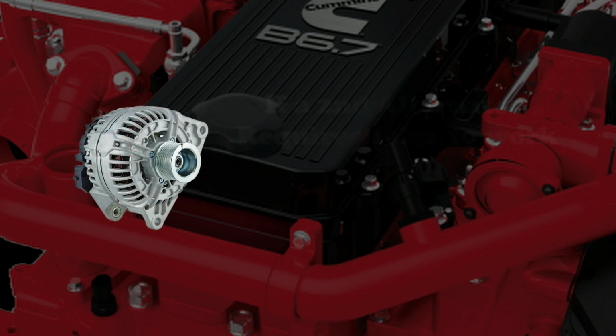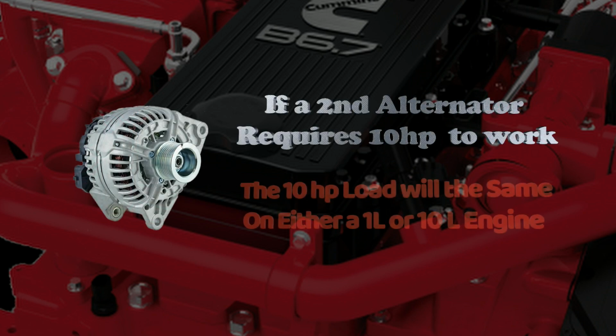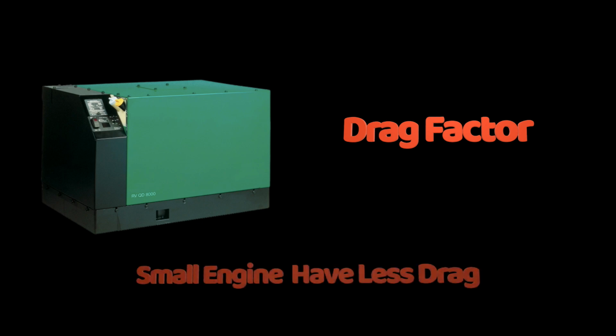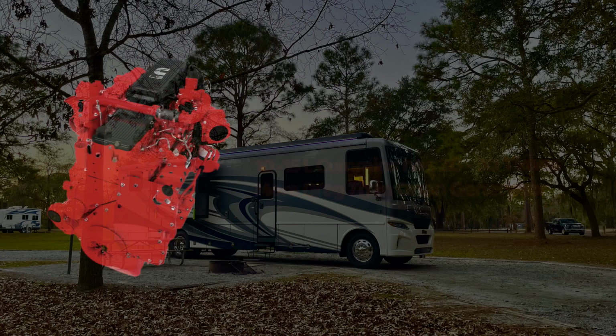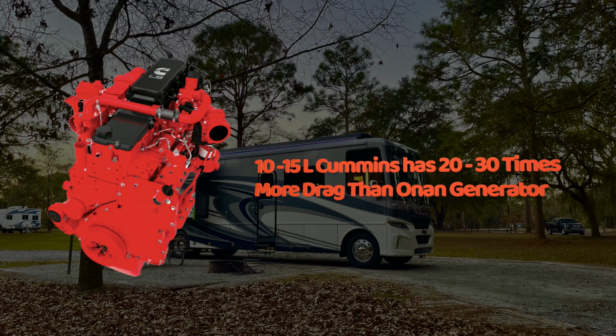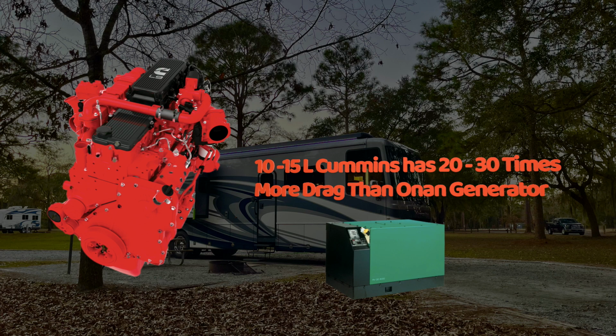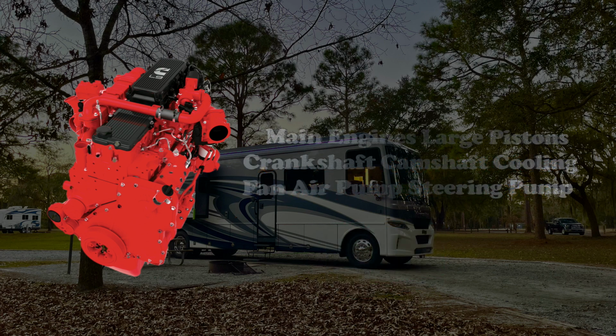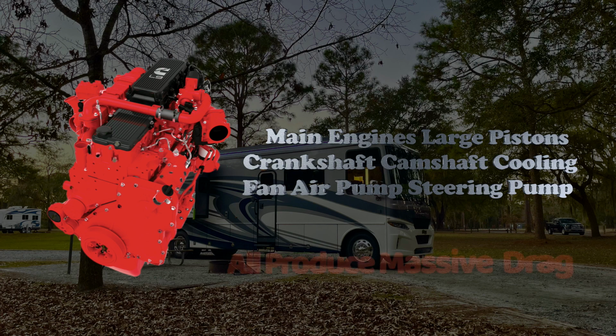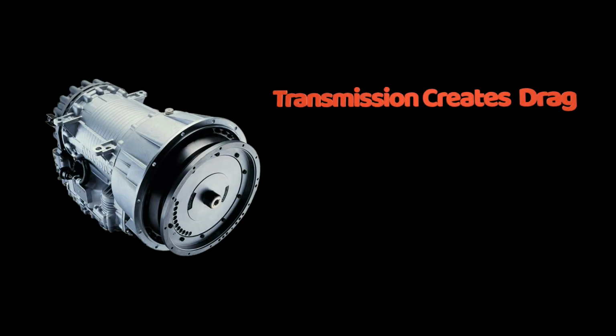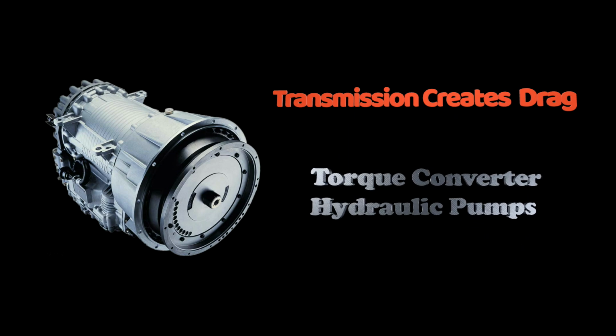If an alternator takes 10 horsepower to turn, the fuel needed would be exactly the same whether attached to a 10-liter engine or a 1-liter engine. We also have to consider drag factor. Since small engines produce less drag, they burn less fuel. A 10 to 15-liter Cummins engine will have 20 to 30 times more loss from drag than a 1-liter Onan engine. The main engine's large pistons, crankshaft, camshaft, fan, air, and steering pumps all produce massive drag, which consumes horsepower.